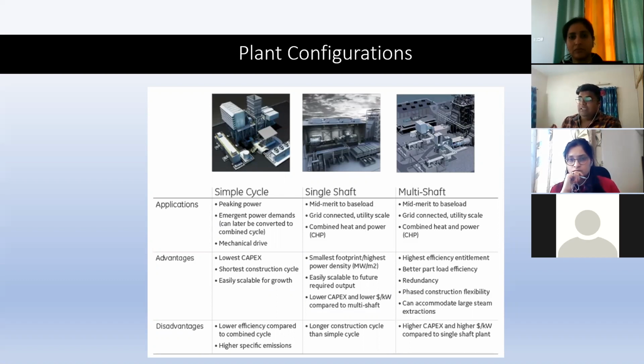Whereas in a single shaft or multi-shaft configuration, also known as a combined cycle power plant, you utilize the heat remaining in the gas turbine exhaust to make steam in a boiler located downstream of the GT exhaust. Instead of letting the flue gas escape into the atmosphere through the gas turbine's exhaust stack, you use that flue gas to heat the boiler and turn the water in the tubes into steam, which is then used in a steam turbine for further power generation. That is your combined heat and power cycle power plant.